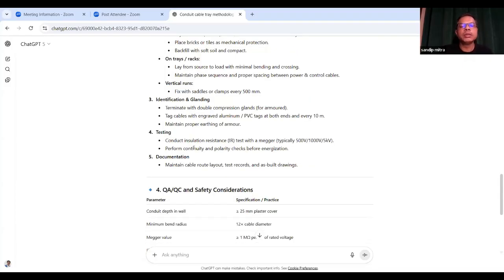Then testing - we are using the insulation resistance test with a Megger and perform continuity and polarity checks.